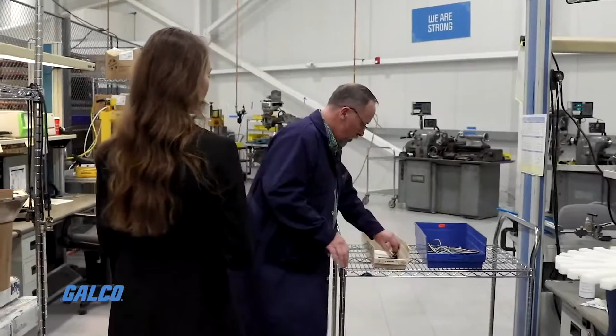Final check. Incoming inspection and final check. So this is what the sensor basically looks like before it's labeled, packaged, ready to go out the door. You can see the crimp on the top. Connected secure. The sensor's checked for the diaphragm, make sure everything looks good. We do a final check for the output of the sensor to make sure that the sensor output on the way out the door is exactly as it was when we calibrated it. We make sure that the auto zero function works. We make sure that aesthetically there's no issues, as the sensor hasn't been dropped.